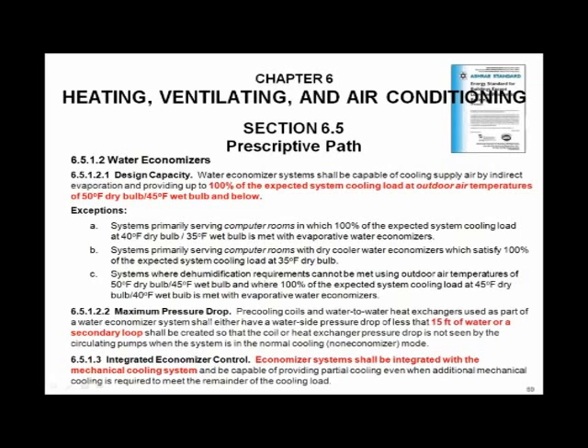What else is in this economizer thing that we should take a look at? The first statement is one we said earlier, to give you the load. Look at what's in red there. The economizer shall be designed for 100% of the expected cooling load with an outdoor temperature of 50-degree dry bulb and 45-degree wet bulb. That's pretty specific. So what you'll be doing is, when you get your cooling load computer system running, you need to take your cooling loads and dump in there 50-degree dry bulb, 45-degree wet bulb as a design point and get the load at that condition, because that determines the size of your economizer.